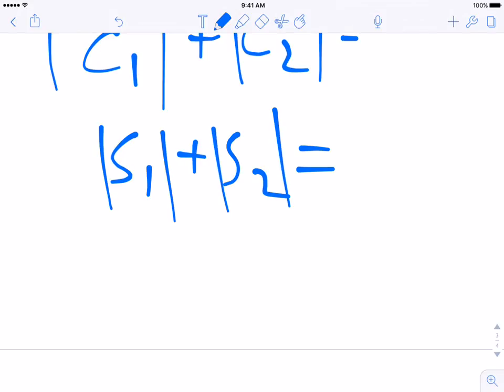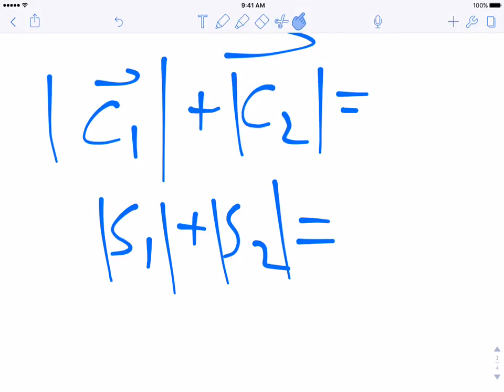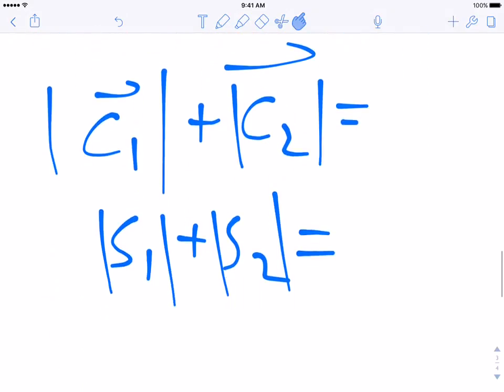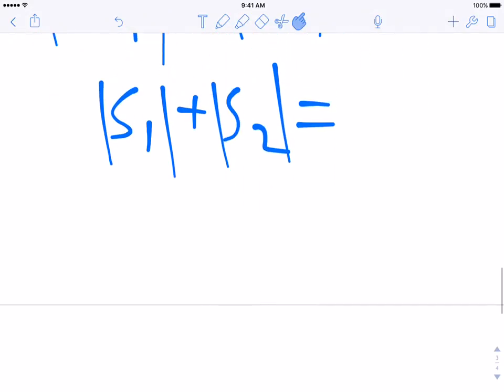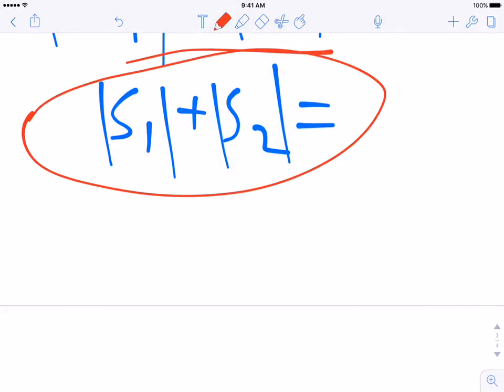Right? So you can't just know that, oh, S1 is 100 MVA and S2 is also 100 MVA, so it's 200 MVA. That's not how it works. You got to find out what's your real and what's your imaginary for each S, and then add them together using this method. So you can't just add S1 and S2. I think this is a common mistake, trying to just add the two MVAs together. That doesn't work.